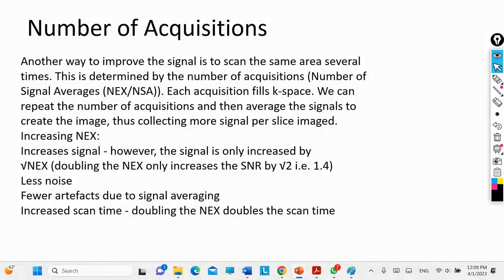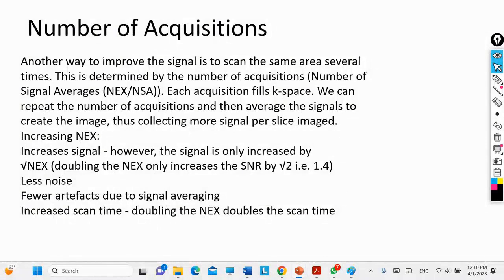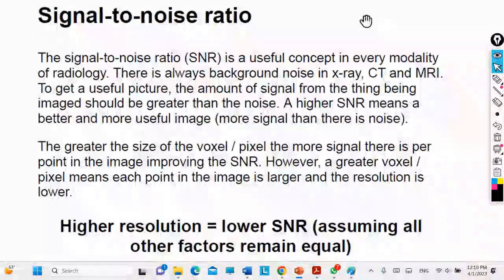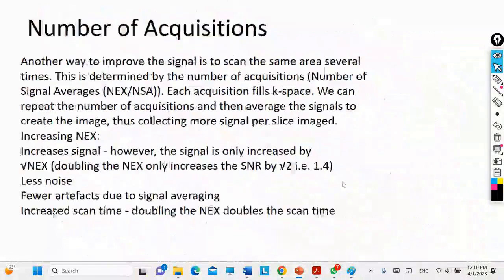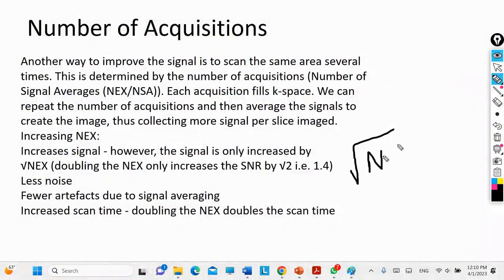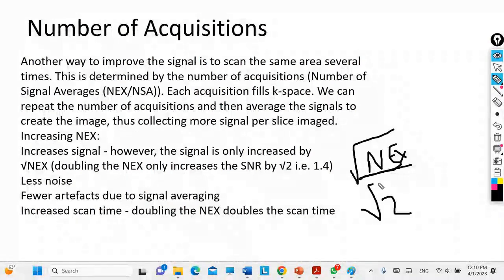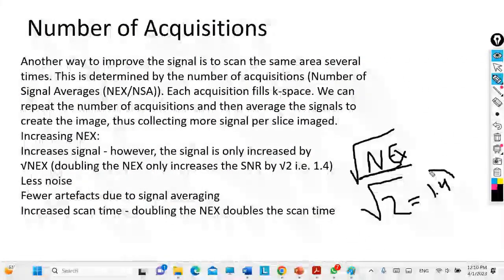Increasing the scan time may lead to motion artifacts since the patient may not remain still, causing blurring. The relationship between SNR and NEX is proportional: the more you double the NEX, the more the SNR increases by the square root of that amount. For example, if you double the NEX from 2, the square root of 2 is approximately 1.4, meaning you improved image quality by about 1.4 times.